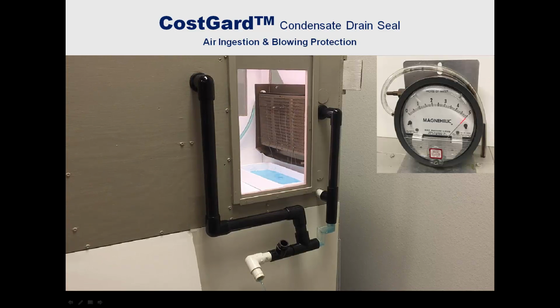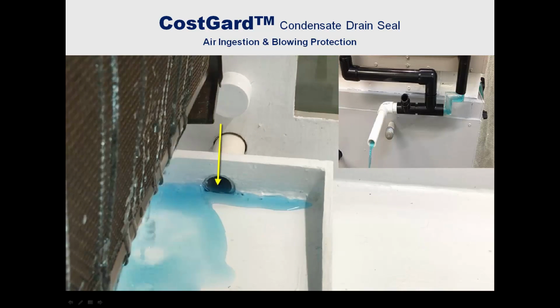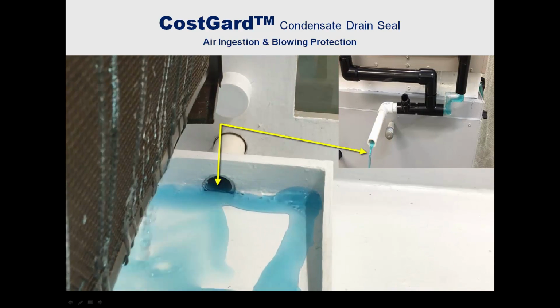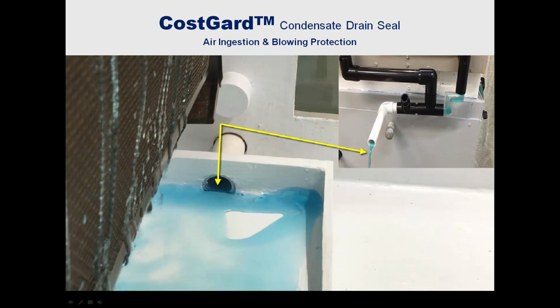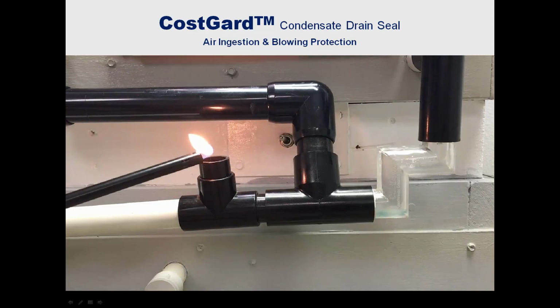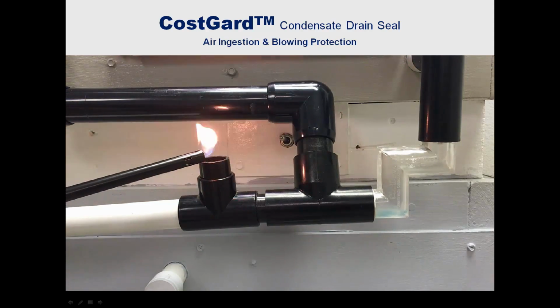CostGard condensate drain seals will operate successfully with internal negative pressures of 5 inches of water. The CostGard device being demonstrated here is operating at a negative pressure of 1.5 inches of water, typical of air conditioning systems up to 30 tons. Note the two views. Observe that there is no blowing of condensate and that flow discharge is smooth. Note also that the benzene lighter flame is being blown away, thus air and pollutants cannot enter through the drain connection.